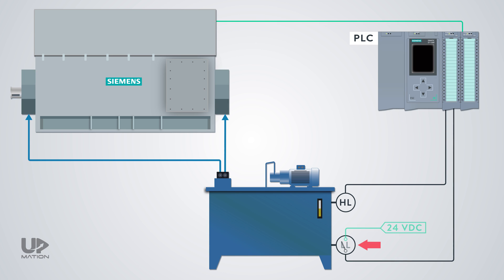Now, let's consider the low level switch is a normally open one. And when the oil level is normal, the switch is sending a 24V DC signal to the PLC.